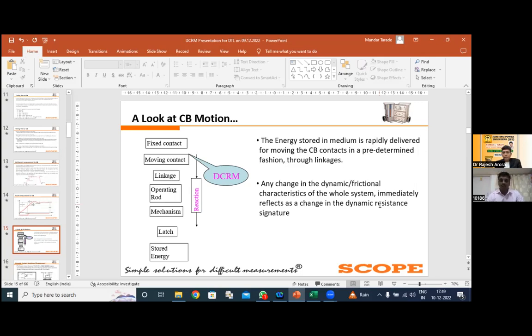If anyone in the industry is not aware of the linkage ratio, then it's my sincere request to all of you: simply place 1 as the linkage ratio and perform the travel operation. And after getting the travel traces, once you get the value of the linkage ratio, you can feed it in, and accordingly you can get the exact contact travel value calculated.